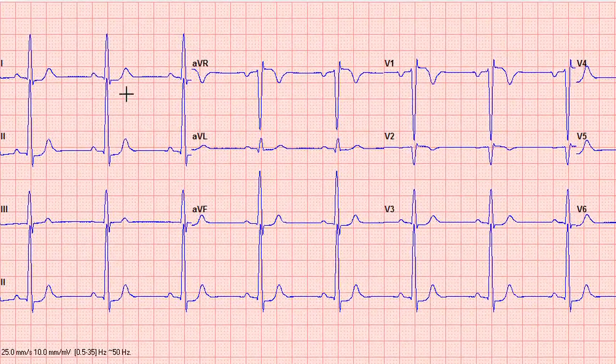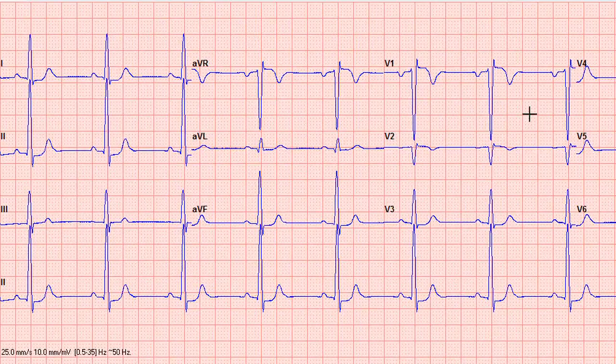After recording the ECG, the test is automatically saved to our software and a PDF copy of the test can be sent to your file output directory. And from there, it can be attached to the individual's patient record. The standard format of the ECG will be three lines with four leads on each. And at the bottom, a lead two rhythm strip.